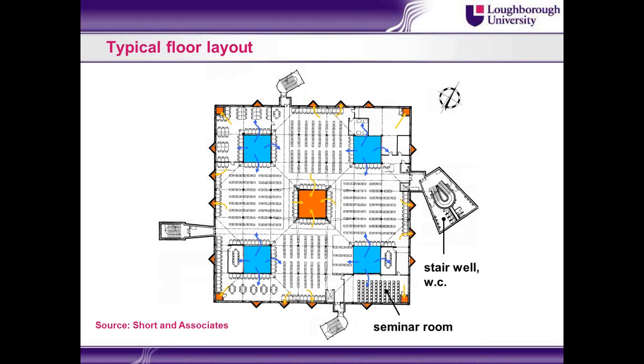So here's what the team came up with, and I just give acknowledgement to the architect Short and Associates here. So this is a typical floor layout, which was 50 meters by 50 meters, punctured by 5 light wells. So we've got a central light well here, a light well in each of the 4 quadrants of the floor plan, and then about 12 ventilation stacks marked in orange all the way around the outside of the building plan. So very deep plan building, but we're providing provision of daylight through these light wells. These light wells are also providing us with our ventilation strategy.